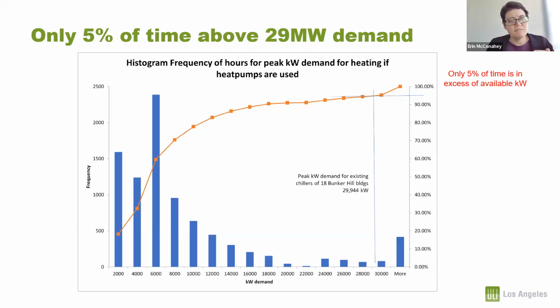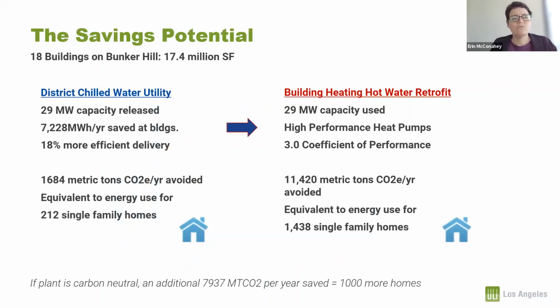So we feel like there's probably a way to take advantage of a chilled water based district cooling system to not only get efficiency on the cooling side, but also to get electrification. And so what would that look like for those 18 buildings? On the district utility side, certainly you have the 29 megawatts that's released for other usage. You have the savings at the buildings. The efficiency of the central plant is much higher because the CenTrio plant is able to run each of the chillers at maximal efficiency and optimization in conjunction with each other. So there's automatically an 18% more efficient delivery than you might have just running off of your own chiller plant.